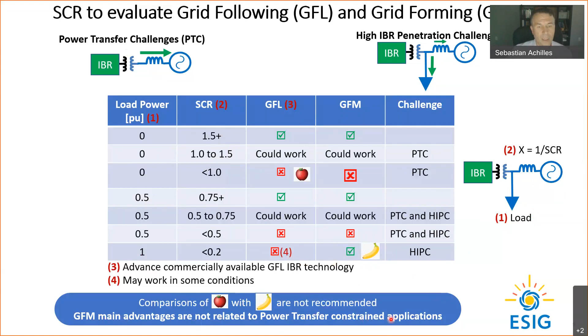if we're looking at this type of challenges of weak grid power transfer challenges, both grid following and grid forming have a similar behavior. There shouldn't be significant expectations that grid forming is going to solve this type of problems. Now, in scenarios where you have an area with very low or no synchronous machines, grid forming will tend to be stable and grid following will not, or not necessarily. So that's one point I wanted to make. So grid forming has important advantages, but not necessarily related to power transfer constraints, which is the most typical way the industry refers to weak grid systems.